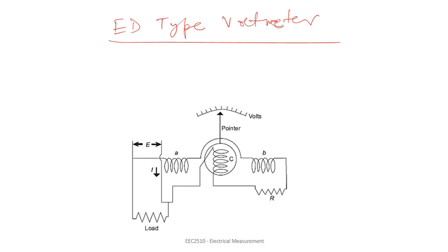If you remember the multiplier resistance that we discussed for the PMMC type instrument, just to increase the range we can add a multiplier resistor. This multiplier resistor, denoted here as R, is included in the circuit. When the total resistance of the coils and the required current for full scale deflection are known, the multiplier resistance can be calculated exactly as we did for PMMC type instruments, or the previous instruments. This instrument scale can be read either as DC voltage or RMS AC voltage.